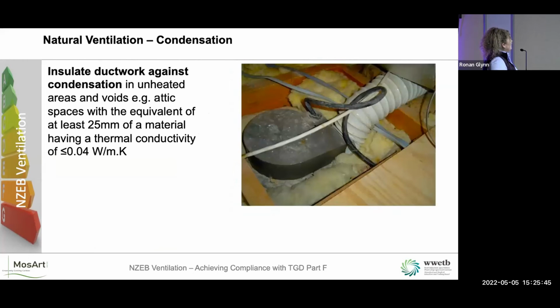So for condensation, for natural ventilation, it's the very same rules. They should be insulated against condensation in unheated spaces with the equivalent of your 25 mil having a thermal conductivity of less than or equal to 0.04 watts per meter Kelvin. So this will be typically what you'd see up in the attic. You have your extract fan come from your bathroom, a bit of flexible ducting, and it's probably sent to the eaves vent or something. So on this particular example here, this is what the homeowner could see. So we have a big damp patch on the ceiling, and it's purely down to condensation because the ducts aren't insulated.